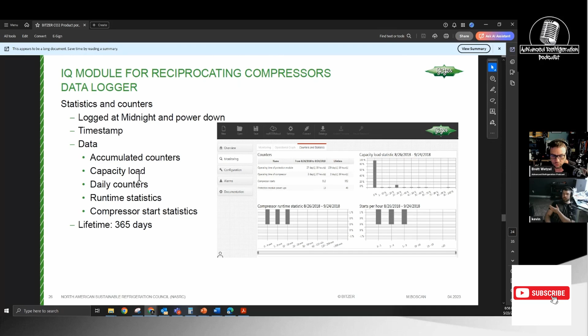So I just did a Danfoss on Thursday or Wednesday. We did some 800A conversions from 255s, and we just copy the programs and I convert them on an 800 and then switch them to 800As. And it copies the program. Danfoss does a fairly good job of the copies. There's hardly issues. So I go to throw them in, and the two apprentices were like, hey, we're testing stuff, and the defrost works, but the compressors aren't shutting off.